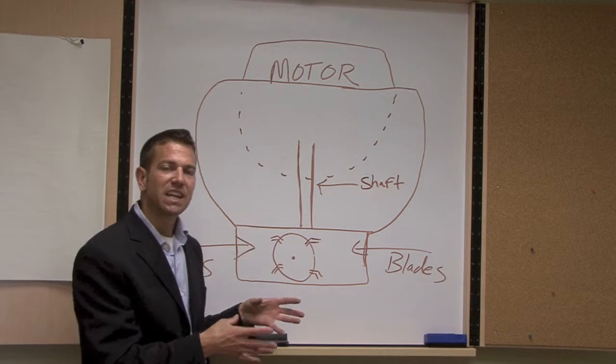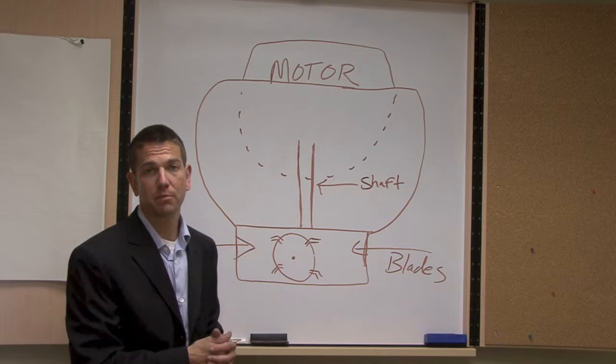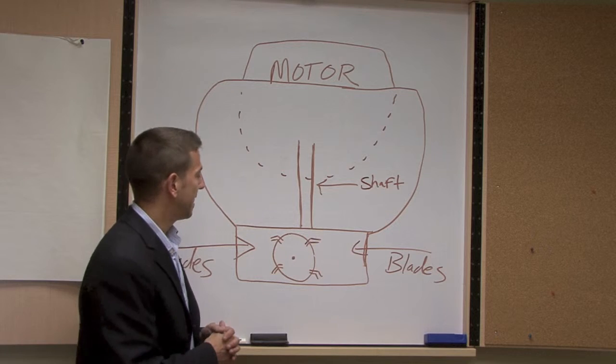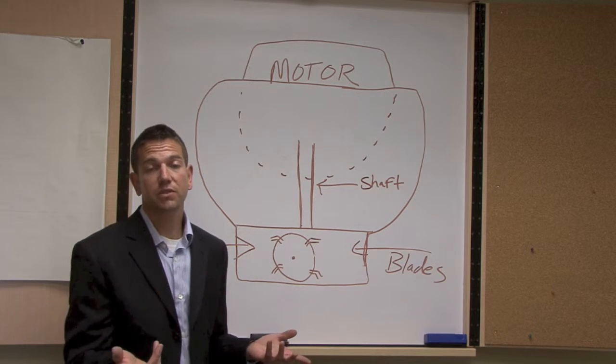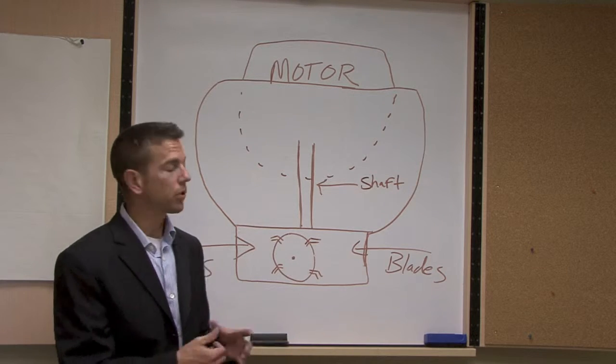Now many times from below we can only clean so far so we need to somehow be able to access those blades in a way that we can clean them of grease so that they don't end up being thrown off balance. Anybody who's had their fan balanced knows that costs a few hundred bucks and worse if it gets so terribly bad they can't balance it and it has to be replaced then you're looking at even more.